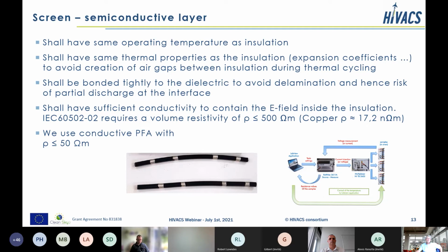For land high voltage cables, a typical value for the volume resistivity is in the order of 500 ohm meter. For the semiconductive PFA we have been using, we have obtained a volume resistivity of 50 ohm meter.